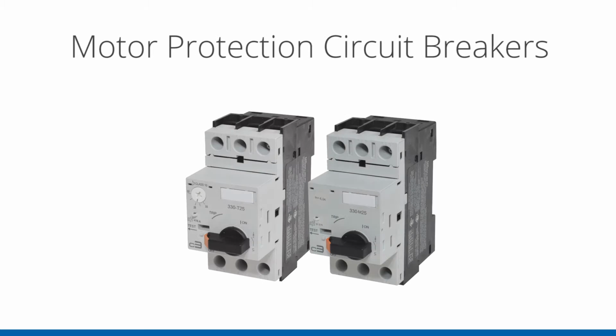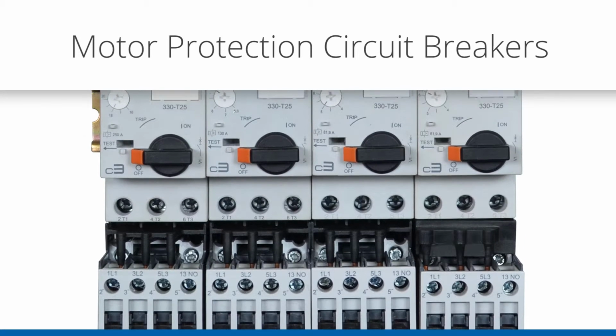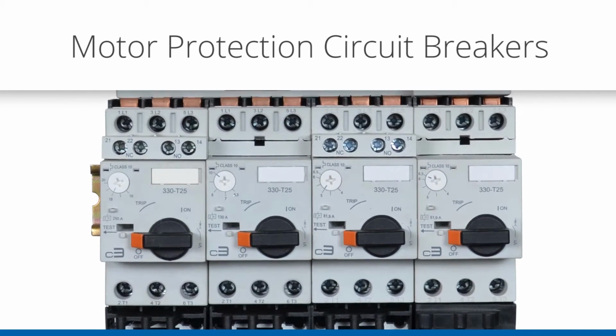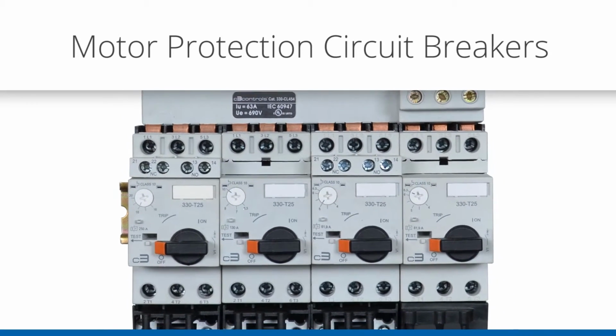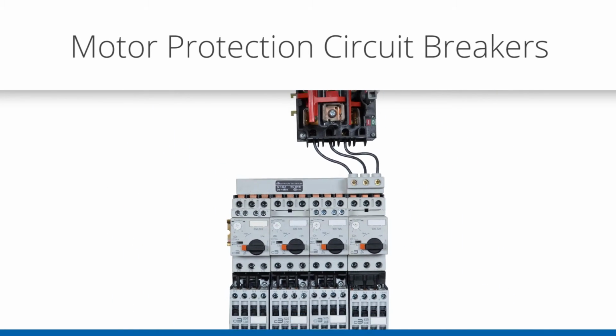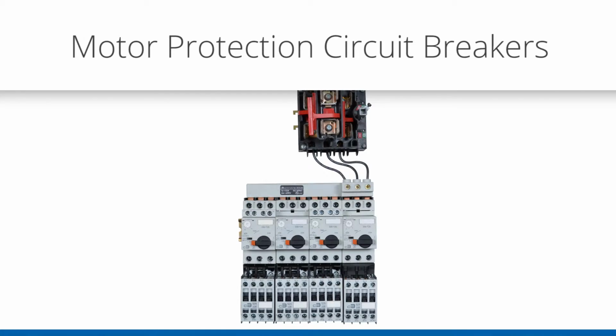Motor protection circuit breakers are multifunction devices certified as manual motor controllers, suitable as motor disconnects, and can be used in group motor installations. They can be used to manually control individual motors and protect them against overload and short circuit currents. And at C3controls, we offer these as standard.